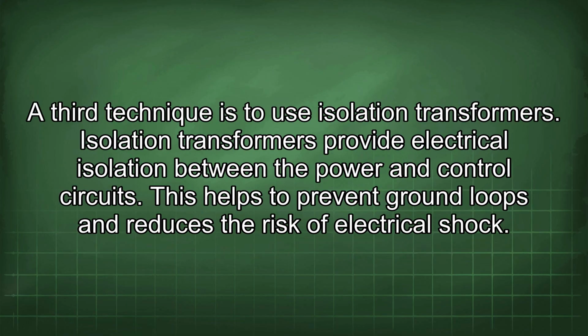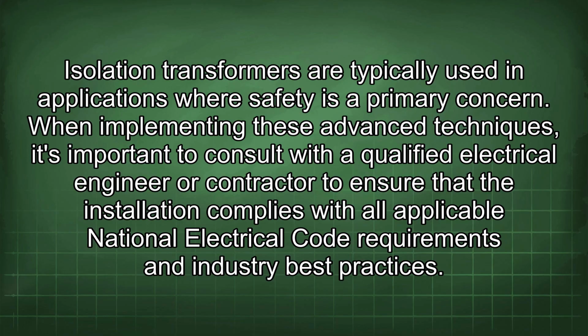A third technique is to use isolation transformers. Isolation transformers provide electrical isolation between the power and control circuits. This helps to prevent ground loops and reduces the risk of electrical shock. Isolation transformers are typically used in applications where safety is a primary concern.